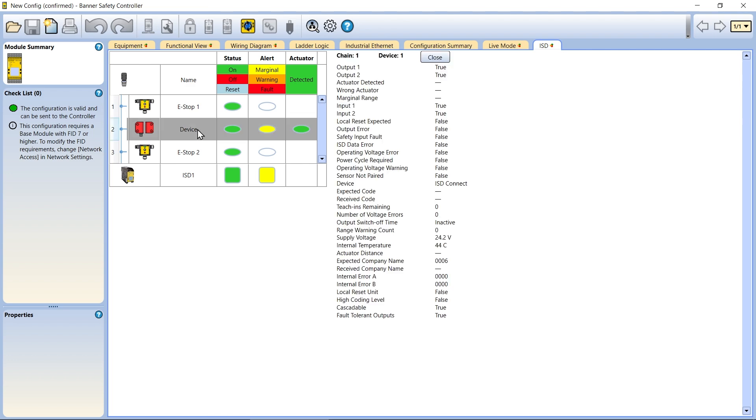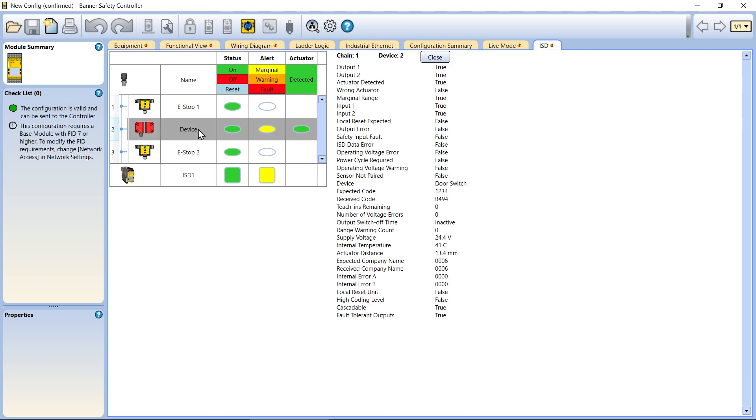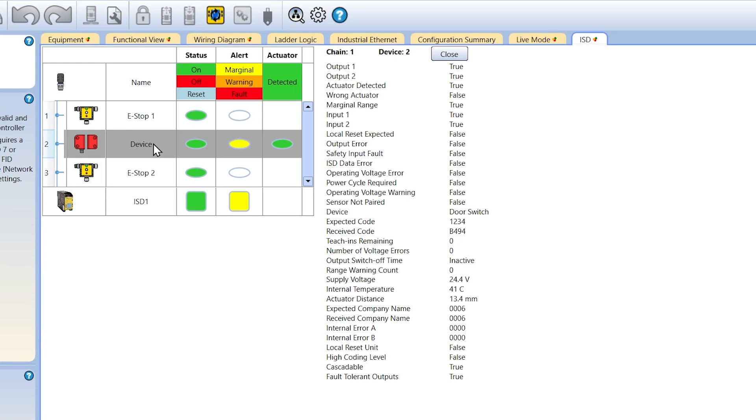By clicking on a device, you will also be provided with extensive diagnostic information. For example, the RFID switches provide information on supply voltage, internal temperature, actuator distance, various error codes, and a plethora of other data.